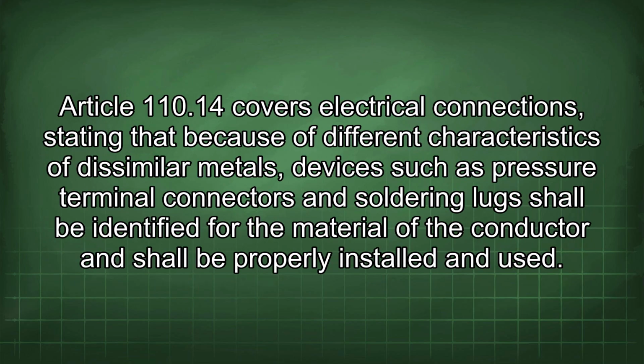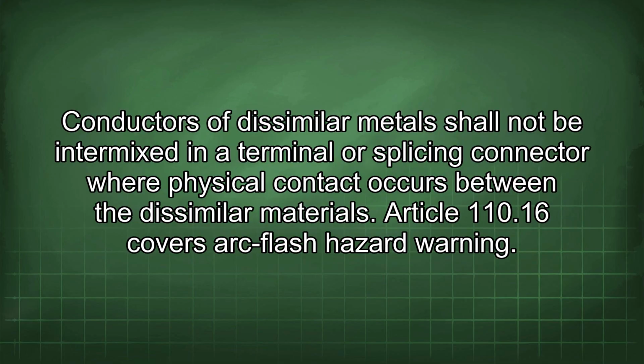Article 110.14 covers electrical connections, stating that because of different characteristics of dissimilar metals, devices such as pressure terminal connectors and soldering lugs shall be identified for the material of the conductor and shall be properly installed and used. Conductors of dissimilar metals shall not be intermixed in a terminal or splicing connector where physical contact occurs between the dissimilar materials. Article 110.16 covers arc flash hazard warning.